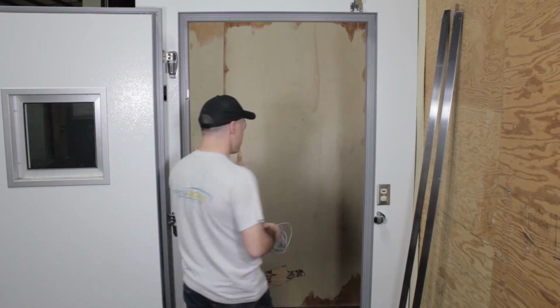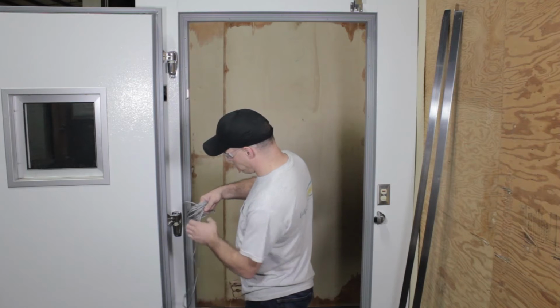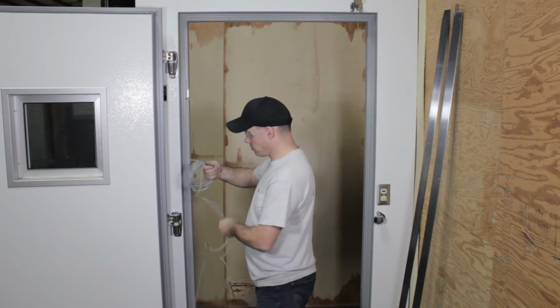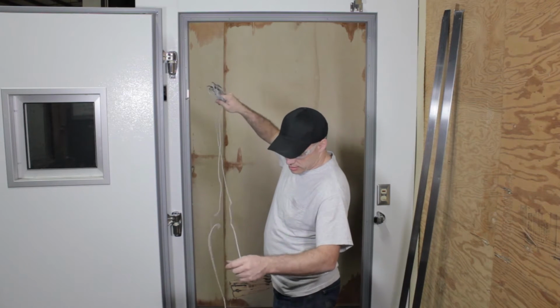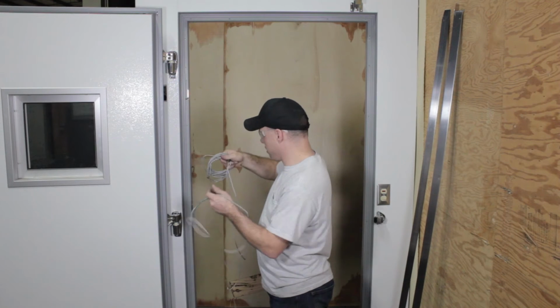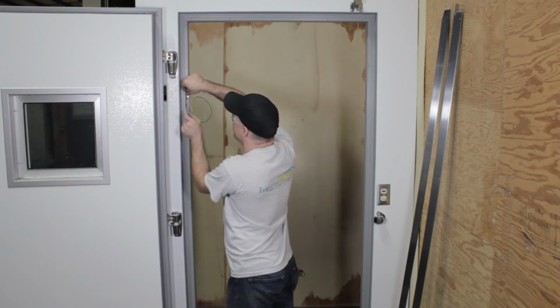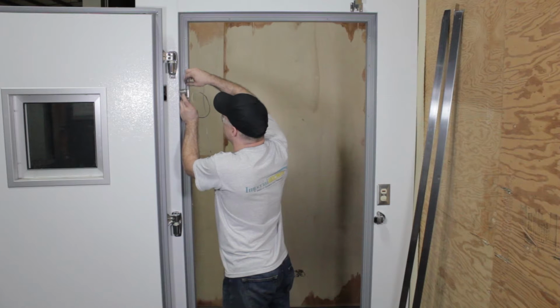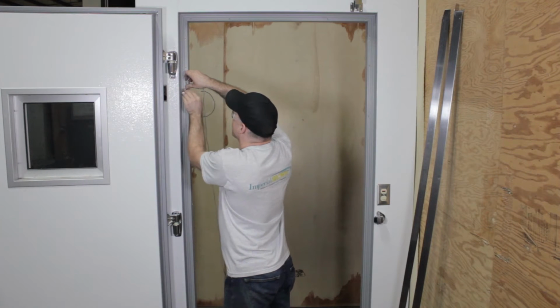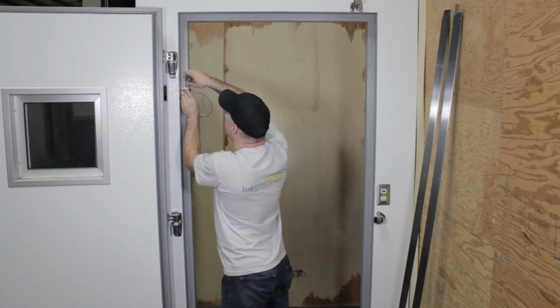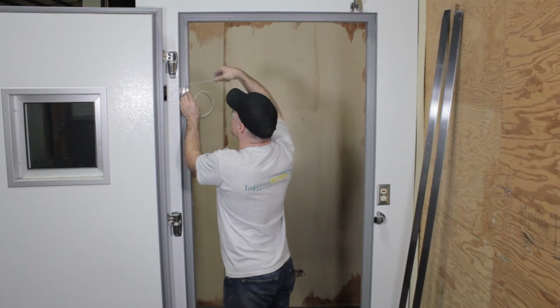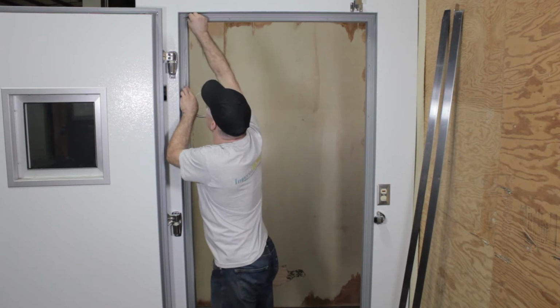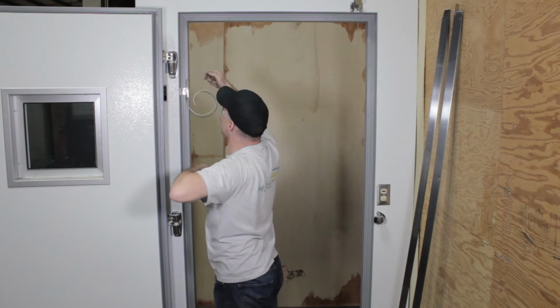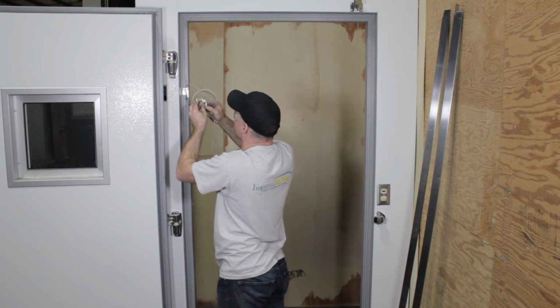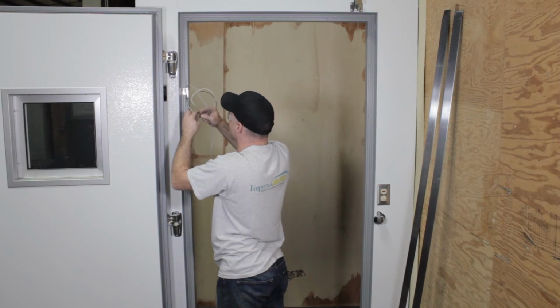Following the old heater cable removal, bring the new heater cable to the door frame and carefully unwind the new heater cable for replacement in the door jamb. Begin placing the new heater cable in the frame with the heater cable electrical leads loose and the heater cable itself in the channel within the frame. Warning: only the heater cable leads should penetrate into the junction box. The heater cable itself should be fully contained in the door frame.